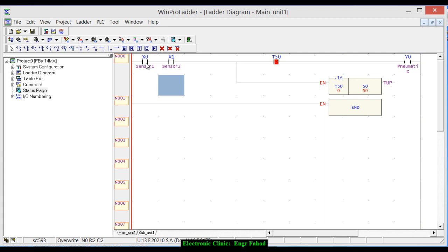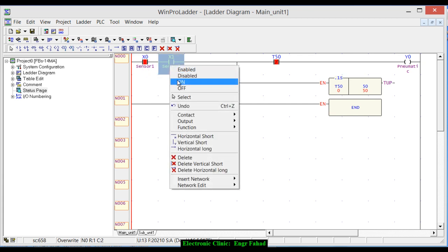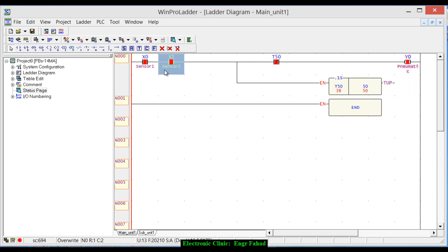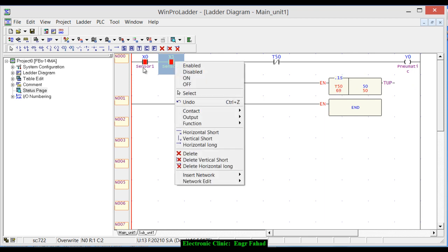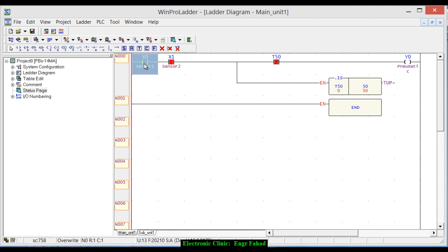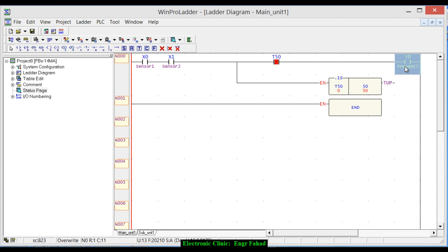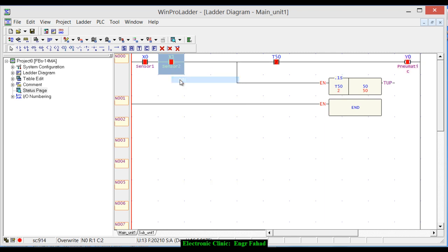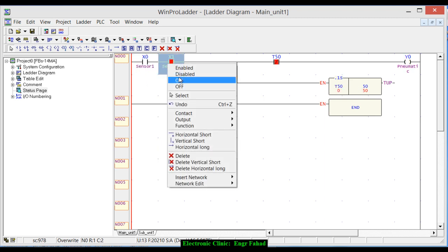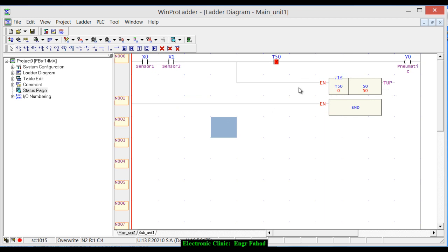Now let's suppose there is a larger box. This sensor is activated, and since the larger box covers both sensors, this one is also activated. You can see both are activated. As the box passes, this one turns off and then this one also turns off — the pneumatic cylinder goes back to its previous position. For another larger box, both sensors activate, the timer runs, and you can see the sorting system working — designed using just a basic AND gate.